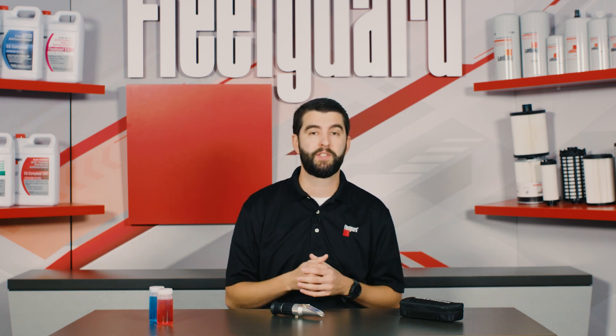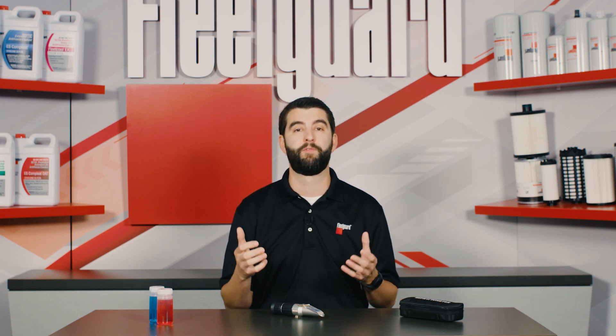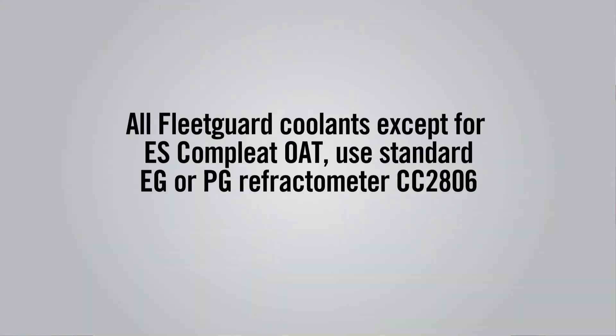Depending on what type of coolant you're testing, you will need the appropriate FleetGuard refractometer on hand, since the viewfinders of each contain different scales for different freeze points. For all FleetGuard coolants aside from ES Compleat OAT, you will use the standard EG or PG refractometer — that's FleetGuard part number CC 2806.